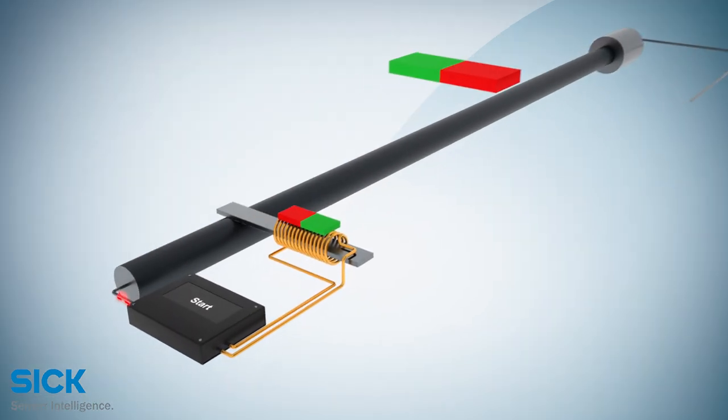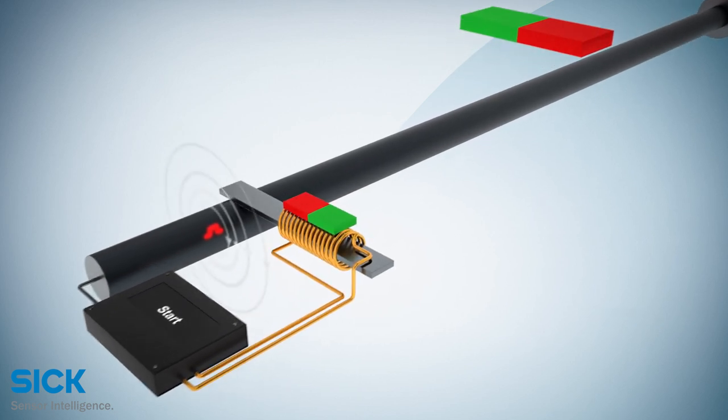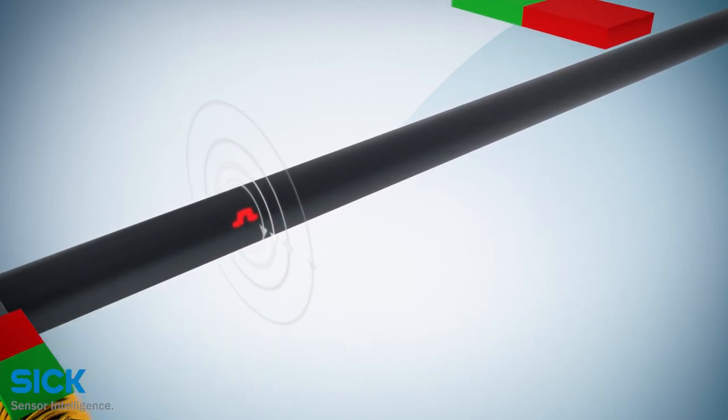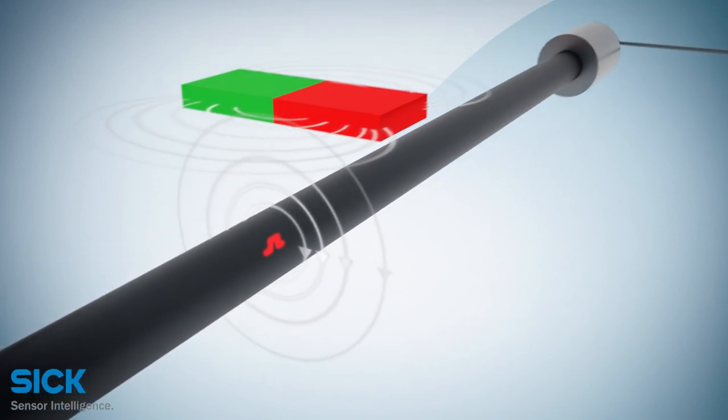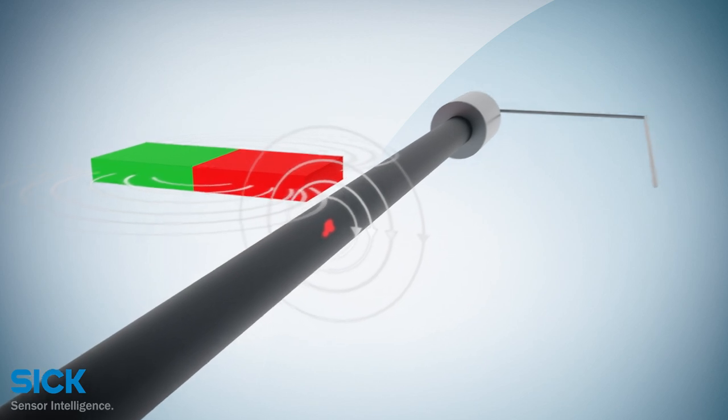A short current pulse is applied to the waveguide and creates a radial magnetic field. The position magnet, which is connected to the movable machine part, generates a magnetic field at its location on the waveguide.